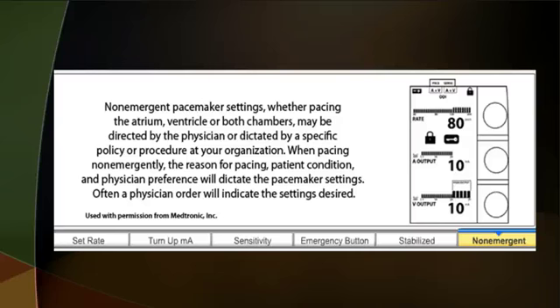Non-emergent pacemaker settings, whether pacing the atrium, ventricle, or both chambers, may be directed by the physician or dictated by a specific policy or procedure at your organization, which I do not believe that we have such a policy in place. So usually it will be your cardiologist or your cardiac surgeon who is telling you what settings they want it to be on. I can tell you, usually with epicardial wires, what I see the outputs on is usually 10, and with the transvenous, it's much smaller than that, anywhere from 2 to 5. Often the physician will indicate the desired settings, and usually that is most always the case.